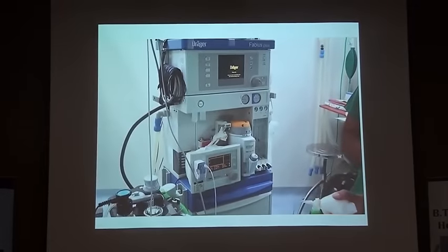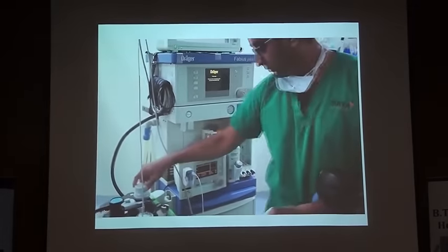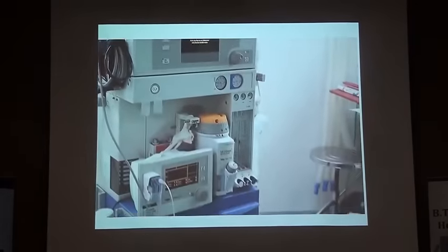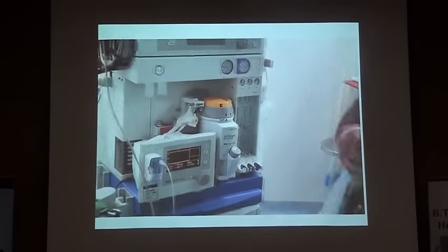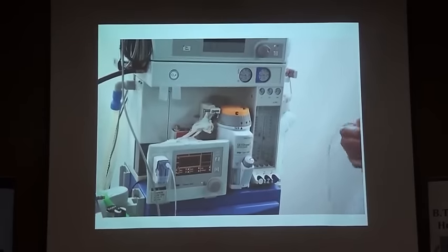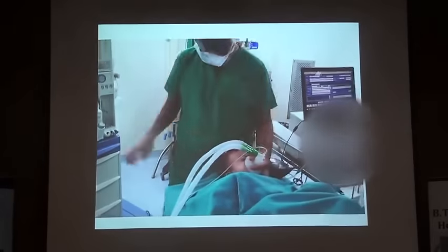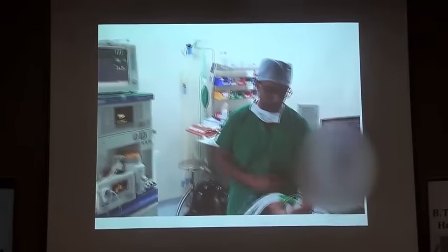You increase the sevoflurane directly to 8%, and you have to empty the bag at least twice or thrice before you put the mask on the child's face. This is because you want to prime the entire circuit. Generally this takes around 30 to 45 seconds. If you have a volume or a gas analyzer, the level should be at least 7% sevoflurane before you put the mask.